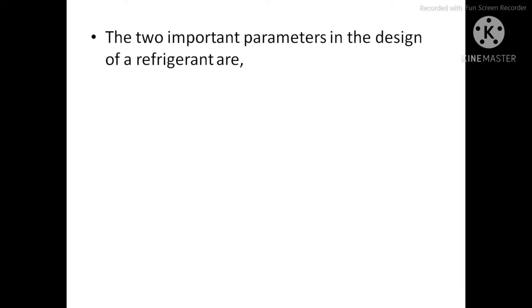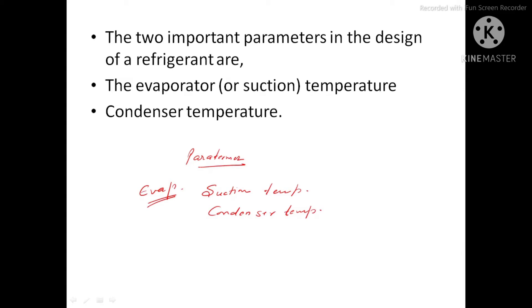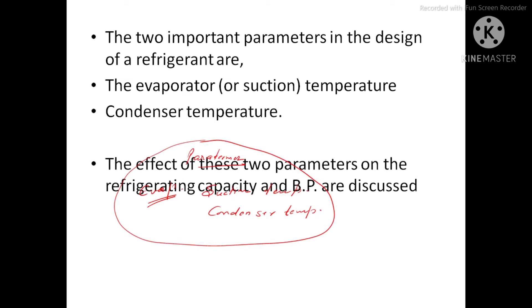Two important parameters in the design of the refrigerant system are evaporator temperature and condenser temperature. The performance of the compressor will be discussed with respect to suction temperature — which is also known as evaporator temperature — and condenser temperature. These two parameters and their effect on refrigeration capacity, total brake power, and brake power per ton will be discussed.